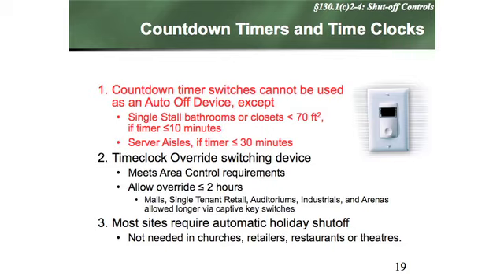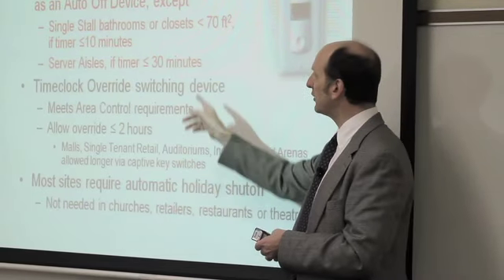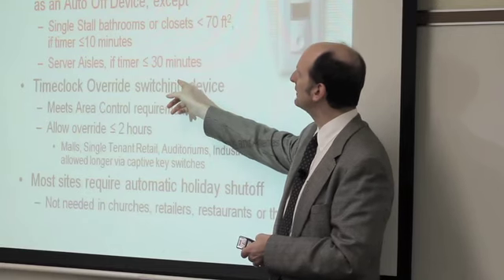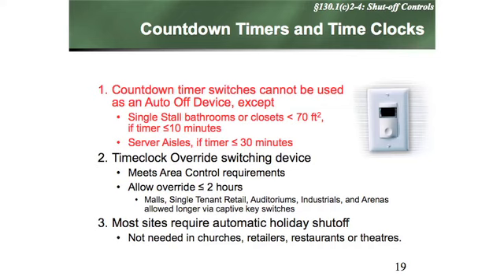Timer switches cannot be used as an automatic off, except in server aisles. You get a lot of airflow in server aisles, with people hiding behind equipment, so you can do it there, but it can only be 30 minutes or less. And this one here I kind of like: for single stall bathrooms, you can have a timer switch.